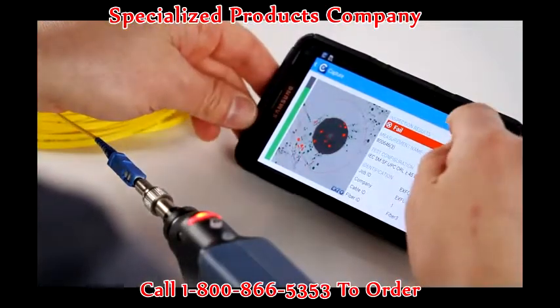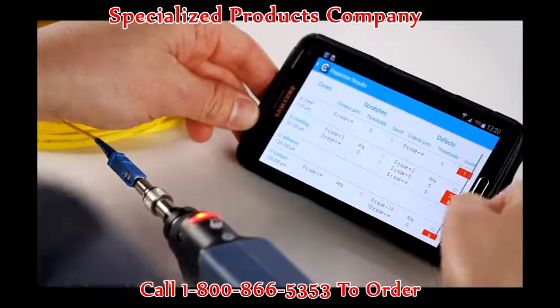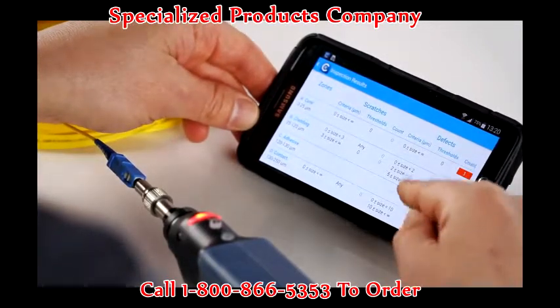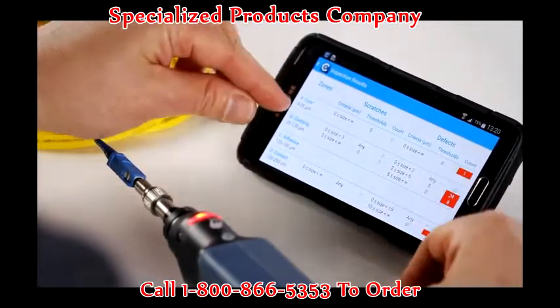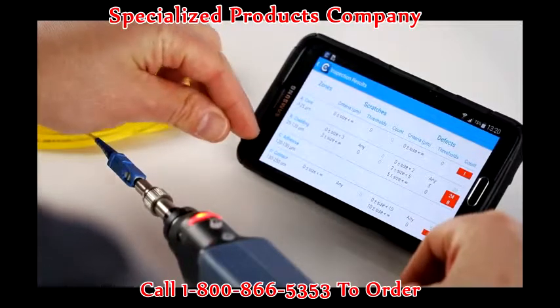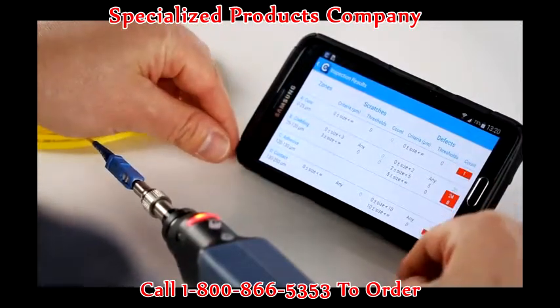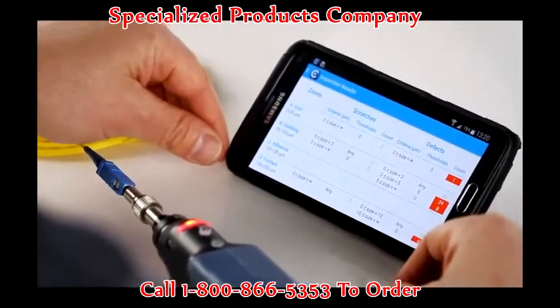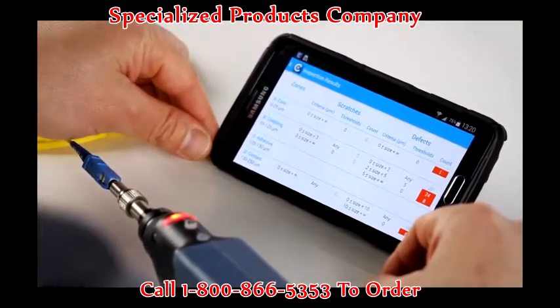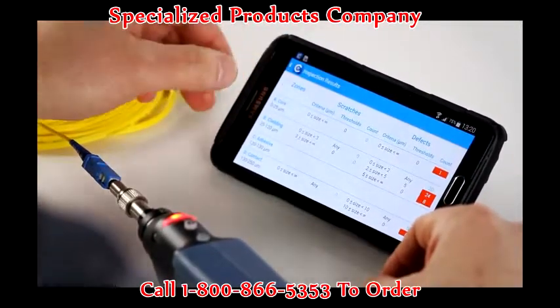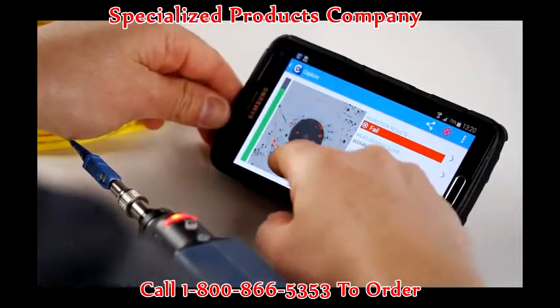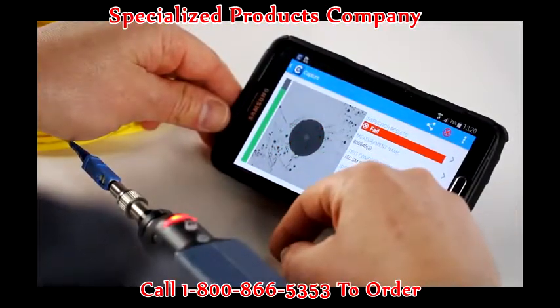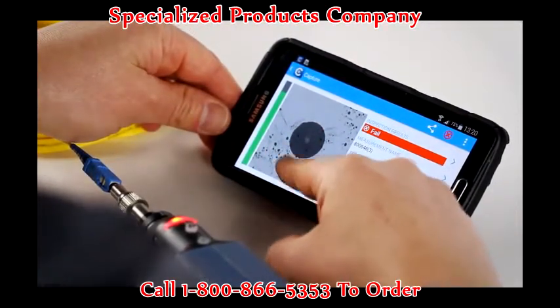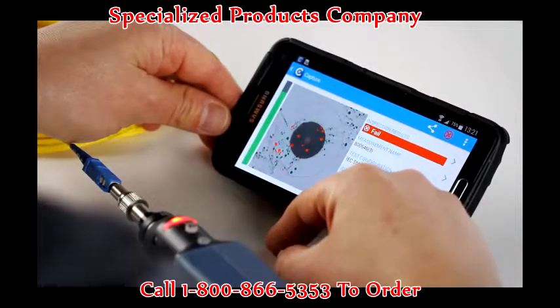If we look at the table here, you can see the number of defects that were found in the different zones, let's say the core, cladding, adhesive, and contact zones, and what triggers the analysis to reject the connector as a fail. An interesting thing you can also do is go back and remove the overlay, so you can just have the connector image, or put back the overlay with the analysis on it.